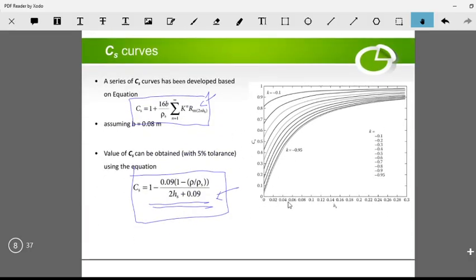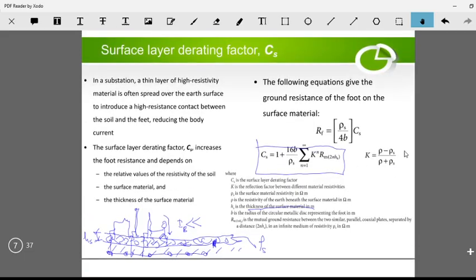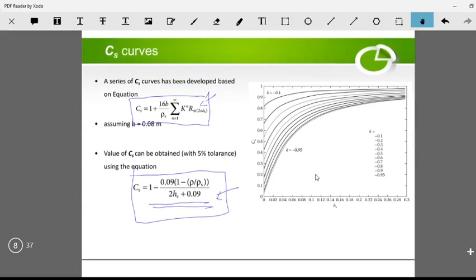This shows how the surface derating factor varies with the thickness of the surface layer, and the parameter k is defined by this graph. You can calculate the value of k using this equation, and depending on the k value and the thickness of the gravel, you can find the corresponding derating factor.